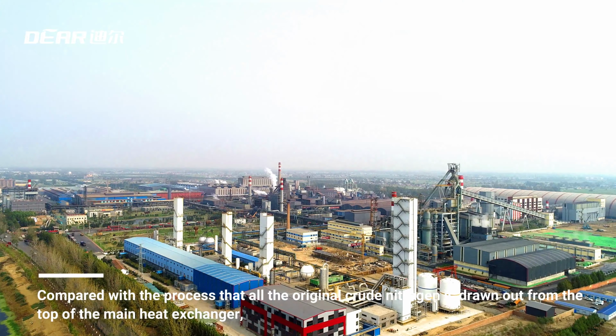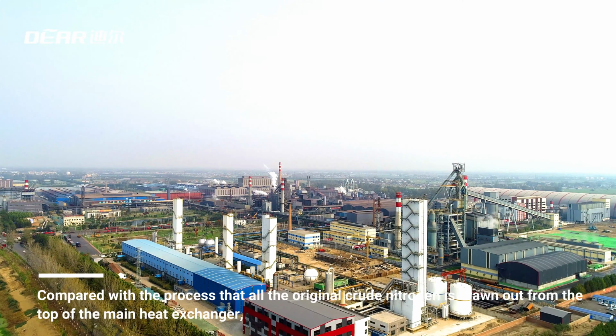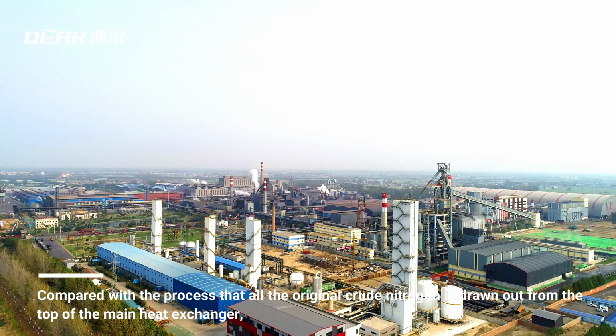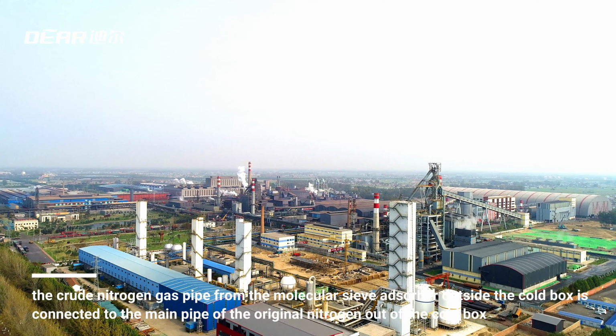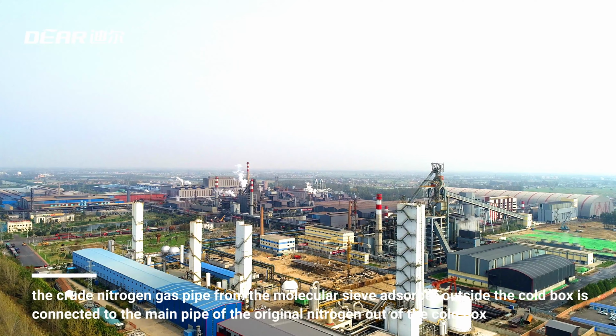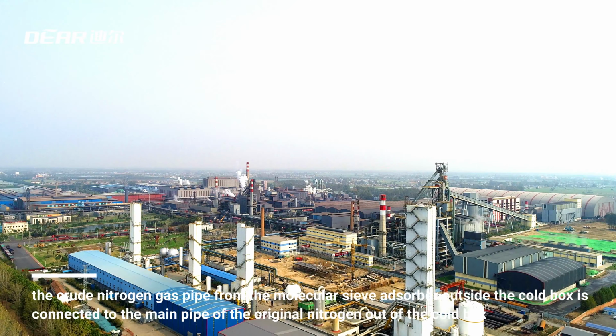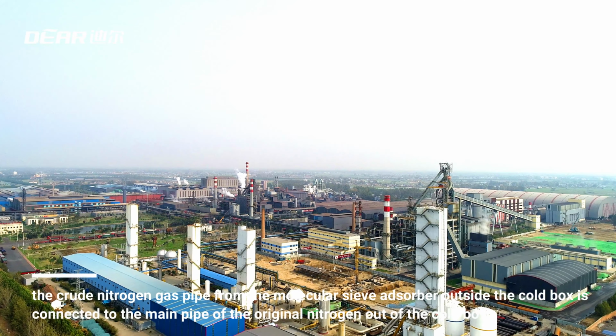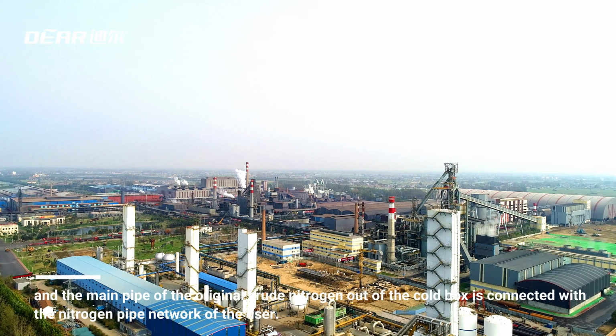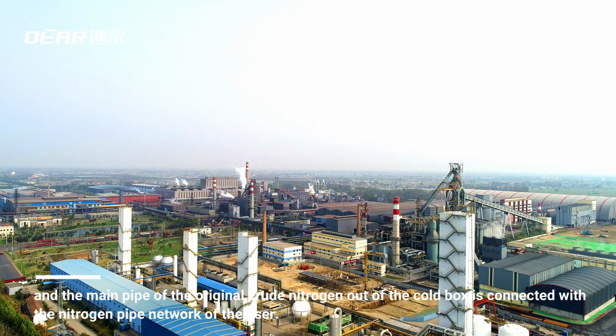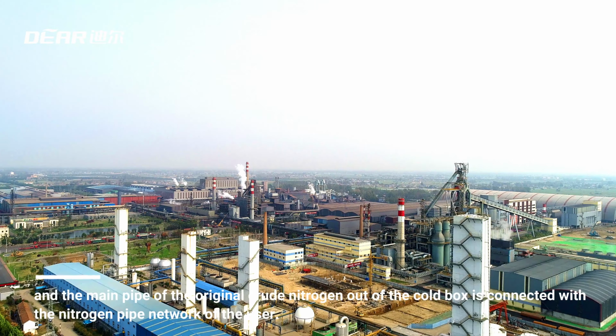Compared with the process that all the original crude nitrogen is drawn out from the top of the main heat exchanger, the crude nitrogen gas pipe from the molecular sieve adsorber outside the cold box is connected to the main pipe of the original nitrogen out of the cold box, and the main pipe of the original crude nitrogen out of the cold box is connected with the nitrogen pipe network of the user.